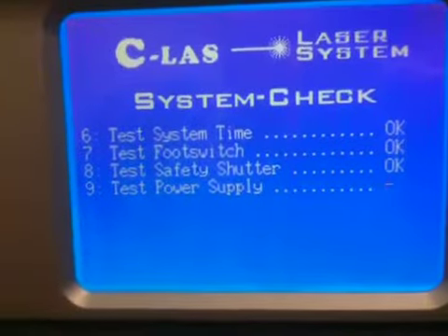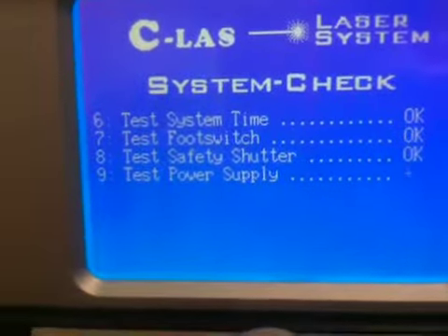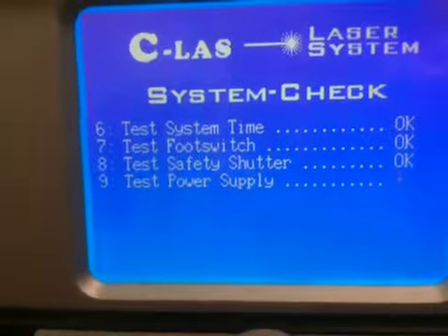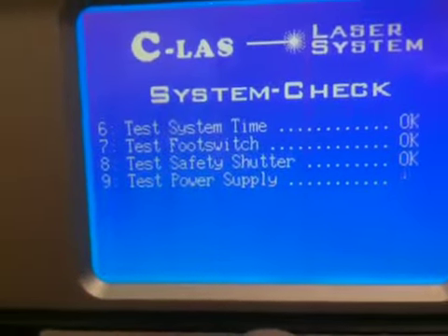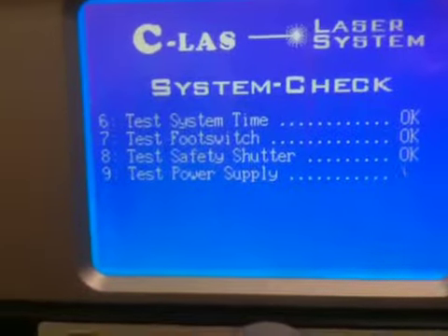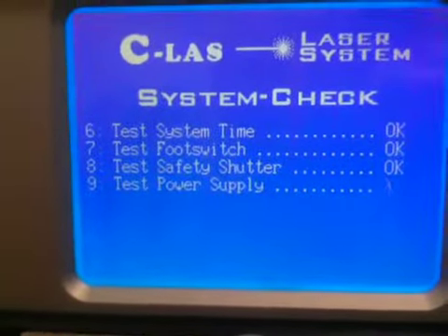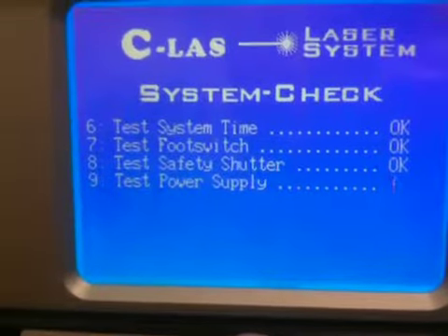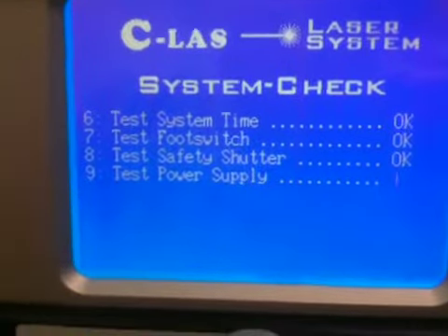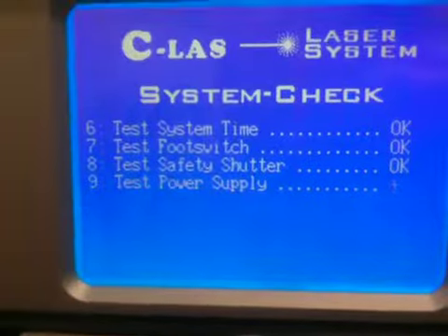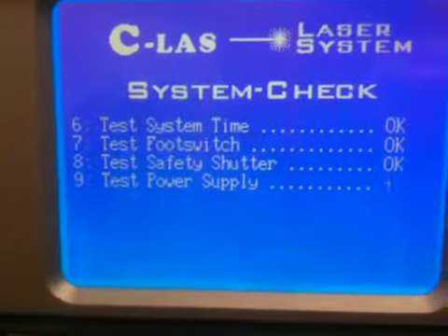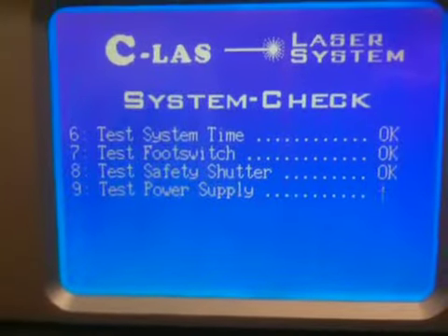So this simulates what they would do in a hospital, what they would see when they start the laser. We want that to be somewhat of a predictable setting. The 1 watt CW or whatever it is, we want it to be very predictable, and we don't want it to be the 999 milliseconds that we have with version 1.5.